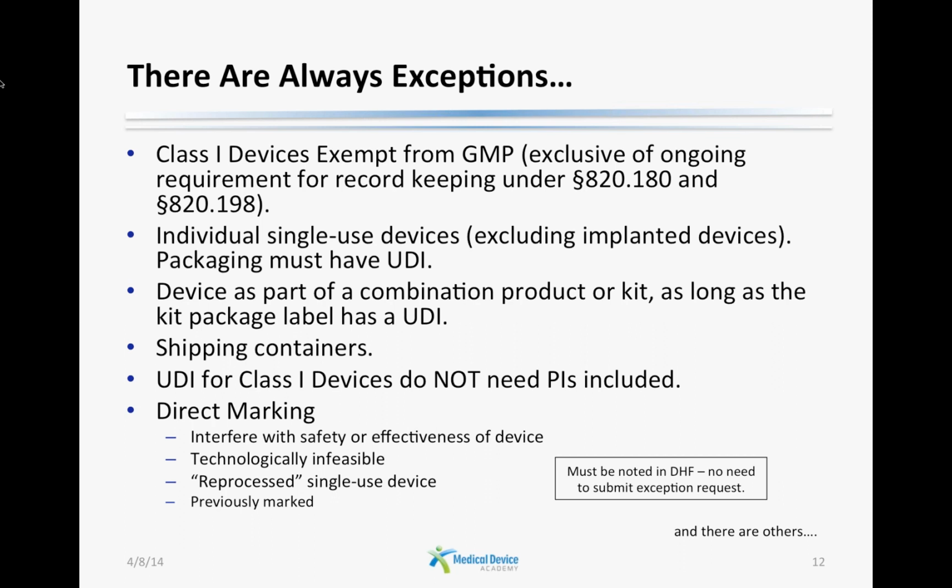In addition, over-the-counter Class 1 devices labeled with a UPC can keep the UPC. These devices will still need to be submitted to the Global UDI Database. The final rule redefined the meaning of UPC in relation to over-the-counter devices. It now meets the requirement of a device identifier.